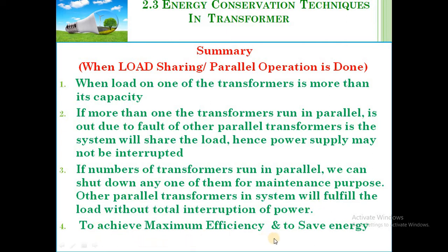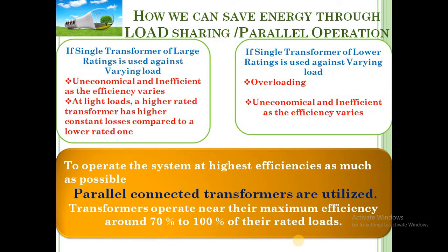And the last, to achieve maximum efficiency and to save energy, we are connecting two or more transformers in parallel. Now, how can we save energy through load sharing or parallel operation? So here I have taken two examples. If a single large capacity transformer is used against varying load, then what will happen? And the second, if a single transformer of lower rating is used against varying load, then what will happen? So these are the two cases which we'll see, and how these two cases can be helped by parallel operation.